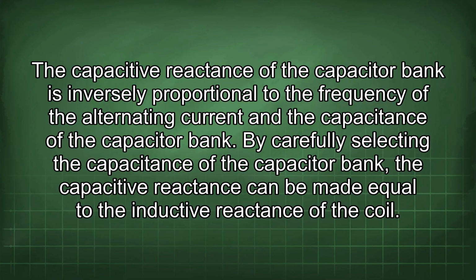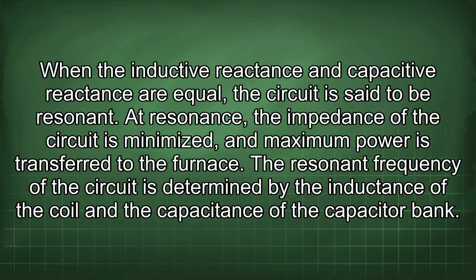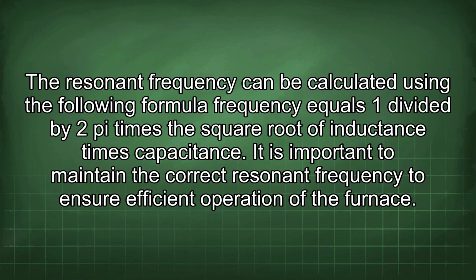By carefully selecting the capacitance of the capacitor bank, the capacitive reactance can be made equal to the inductive reactance of the coil. When the inductive reactance and capacitive reactance are equal, the circuit is said to be resonant. At resonance, the impedance of the circuit is minimized and maximum power is transferred to the furnace. The resonant frequency of the circuit is determined by the inductance of the coil and the capacitance of the capacitor bank. The resonant frequency can be calculated using the following formula: frequency equals 1 divided by 2 pi times the square root of inductance times capacitance.